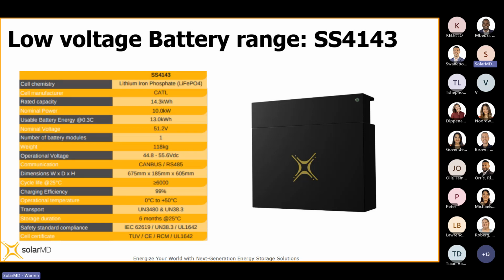With Solar MD, it is possible to mix and match batteries, and we've seen this as customers' needs have grown and they've had more money available to them. They started out on a 3.7, then added a 7.4, and now they've got an 8.3, or they've mixed a 7.4 with a new 14.3 kilowatt hour battery. It is possible to parallel them in that way. Of course, it's crucial how you do the DC cabling to ensure the most even performance of both.